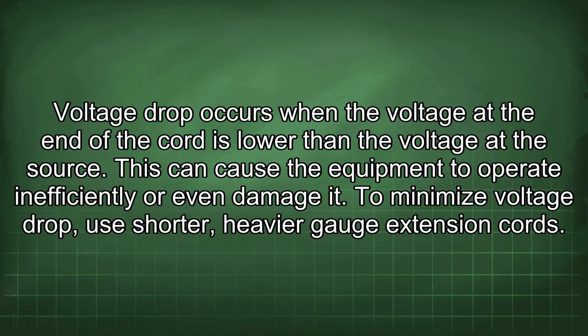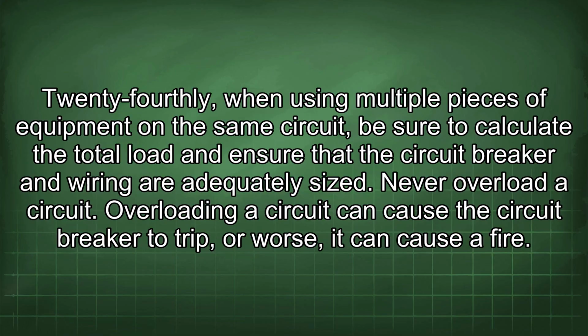This can cause the equipment to operate inefficiently or even damage it. To minimize voltage drop, use shorter, heavier gauge extension cords. 24thly, when using multiple pieces of equipment on the same circuit, be sure to calculate the total load and ensure that the circuit breaker and wiring are adequately sized.